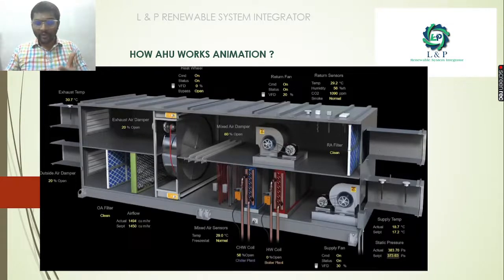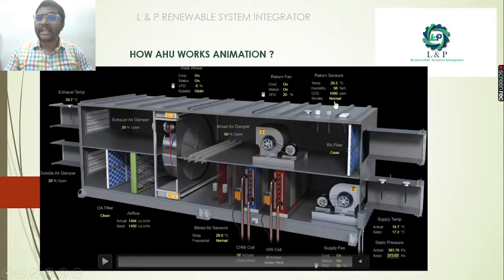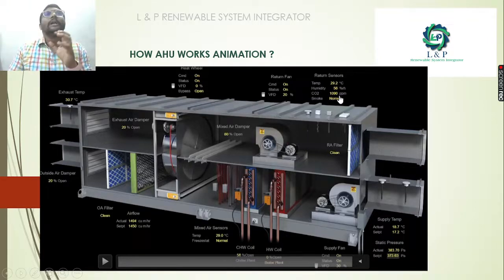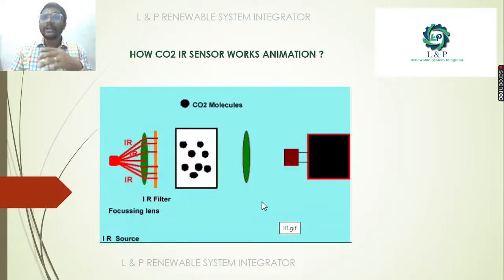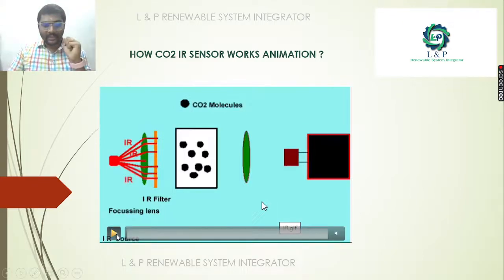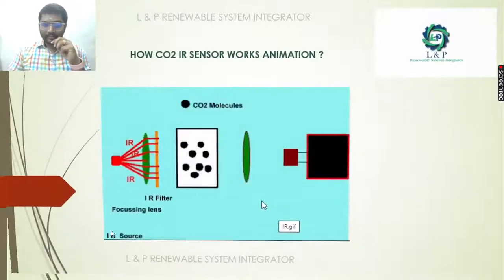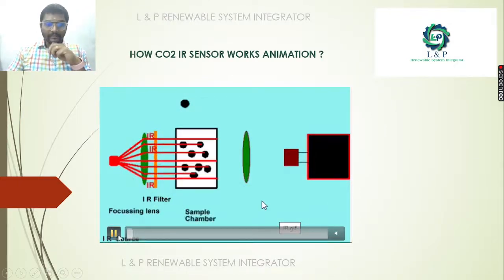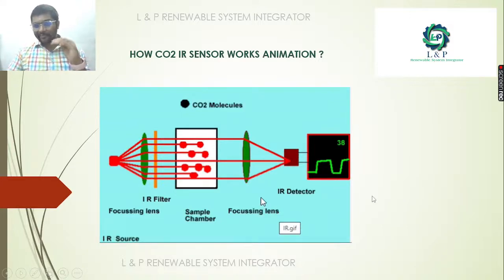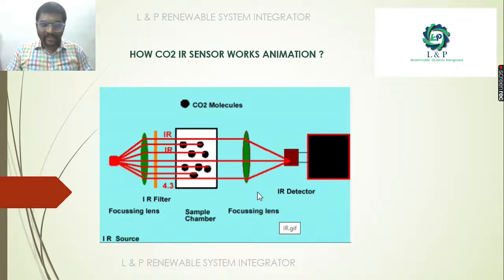Even for air handling units in the return side, a CO2 sensor will be there so we can know how much CO2 presence — how much PPM — is in the return air that we are taking outside. These CO2 sensors use infrared radiation as a source. We can find out CO2 presence inside the gas molecules. We are passing infrared light and CO2 molecules are absorbing it around 4.3 microns. Because of that, whatever we are sending, we won't receive the same 100%. Using this difference, we can easily identify the CO2 presence and the number of CO2 molecules inside that particular building.